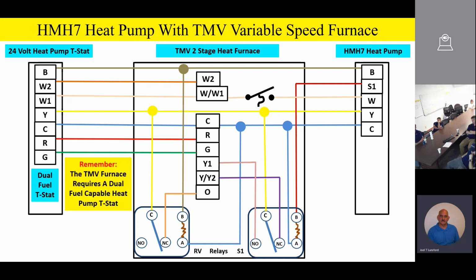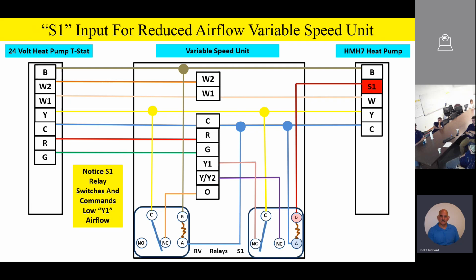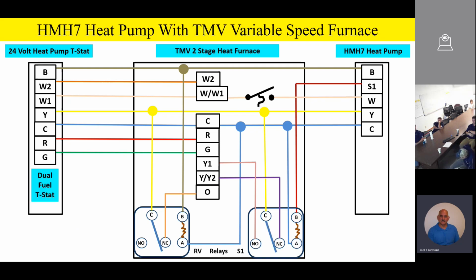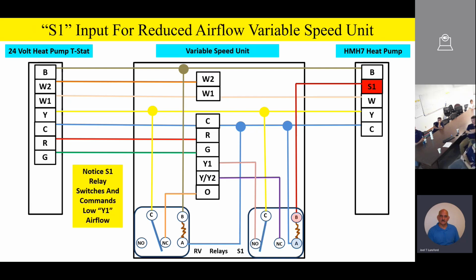Now remember, the TMV furnace requires that dual fuel thermostat like I just said. And as we start getting into some of the switching of the relay, you can look at the animations on how they work. So let's go ahead and look at the animation on the relay on the right-hand side. Bang. Just like we had before, when I go to the S1 output on the outdoor unit, we switch that relay and we command low airflow or Y1 airflow on our variable speed units.